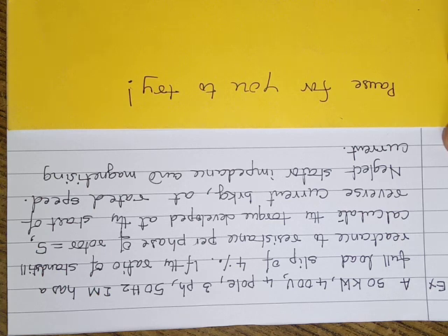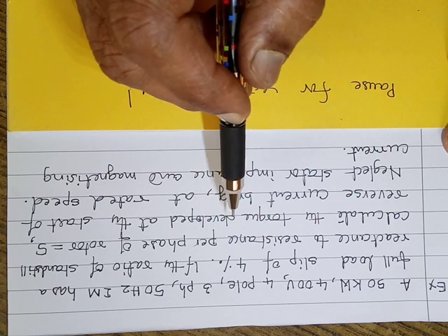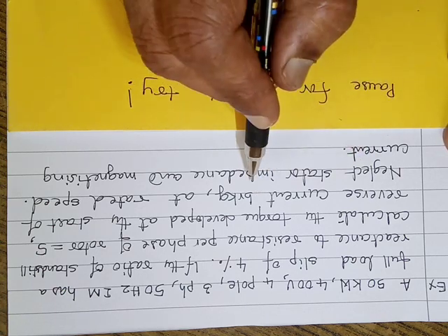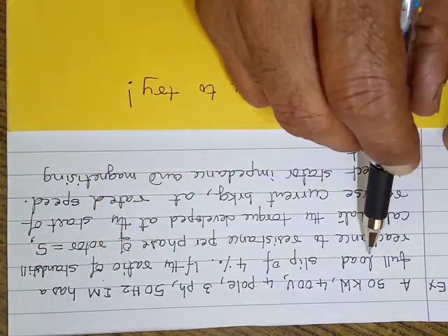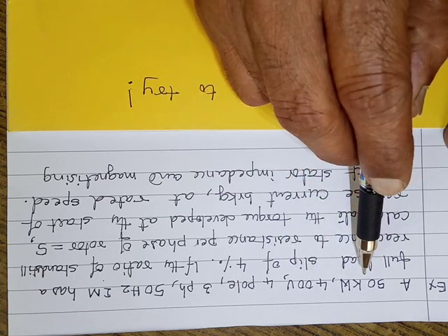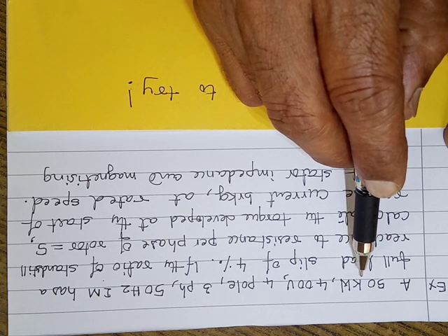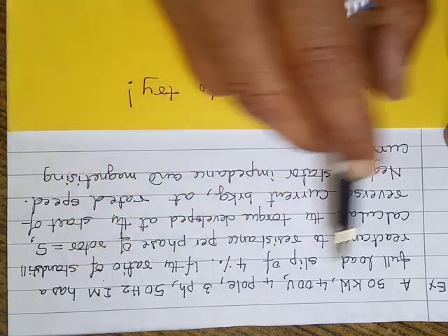Okay. So now look at this problem. It is a problem on braking, reverse current braking. That is the very first thing that we should be clear. It is on braking. It is reverse current braking of a three-phase induction motor. And this three-phase induction motor is with the ratings 50 kilowatts, 400 volts. When it is told about a motor, what does 50 kilowatts represent? Output power. 400 volts line voltage. 4 pole, P number of poles. It has a full load slip of 4%, 0.04.